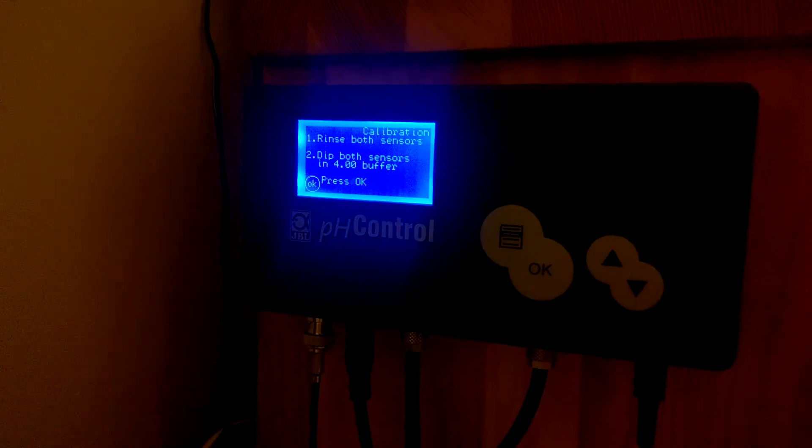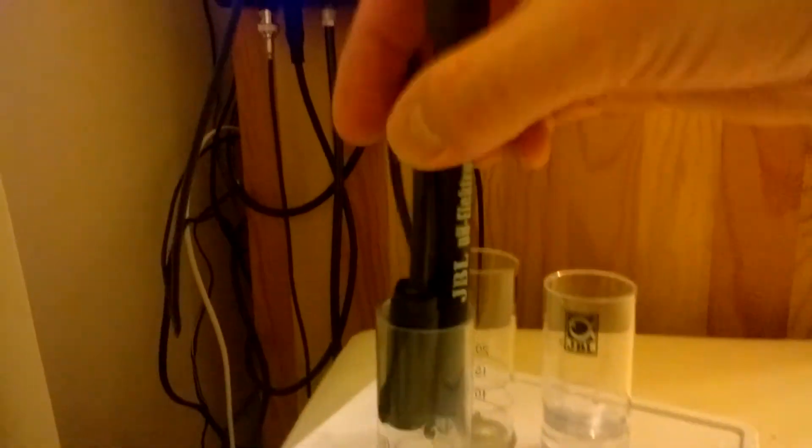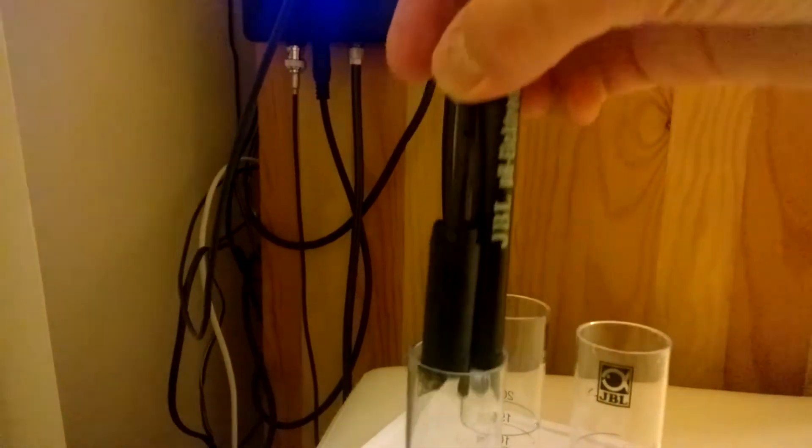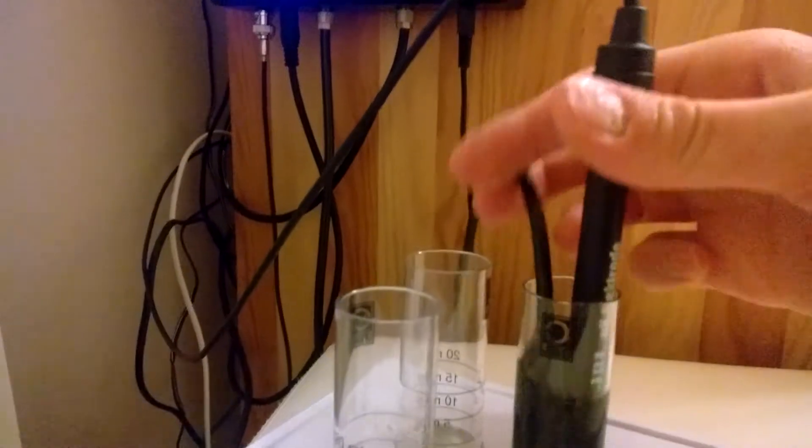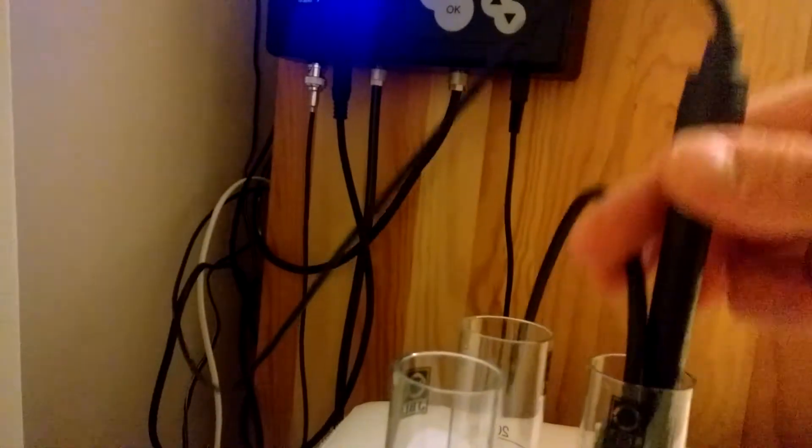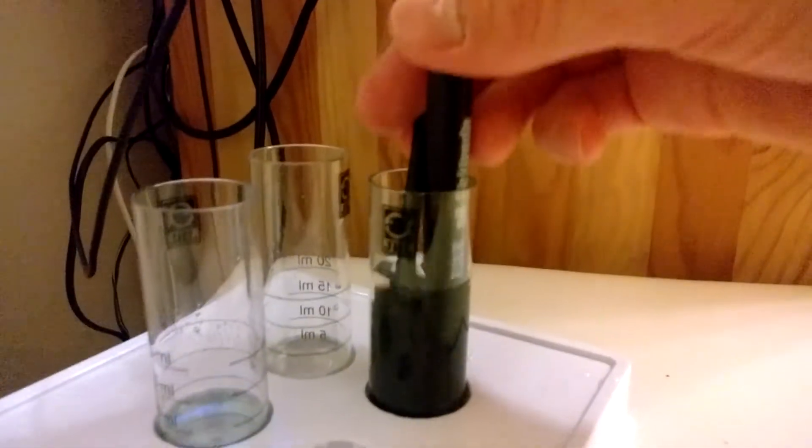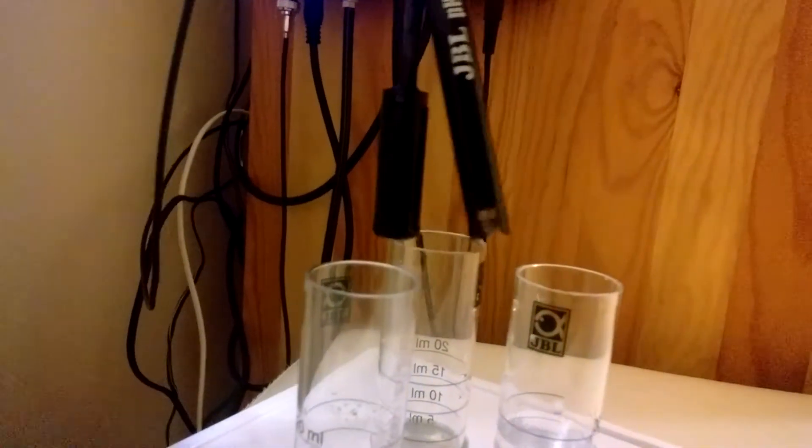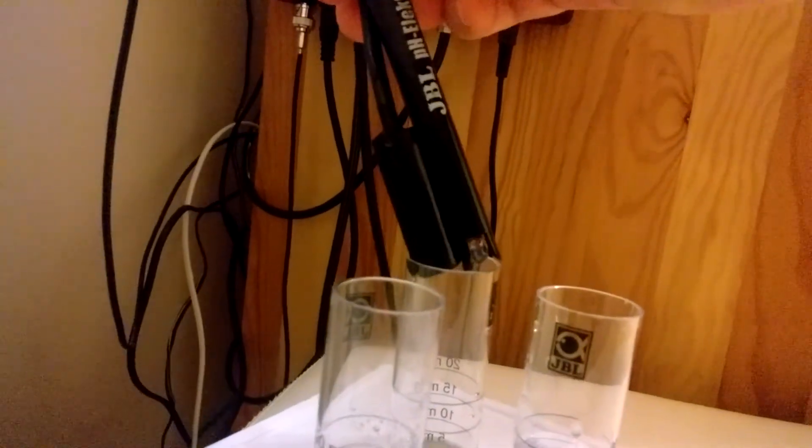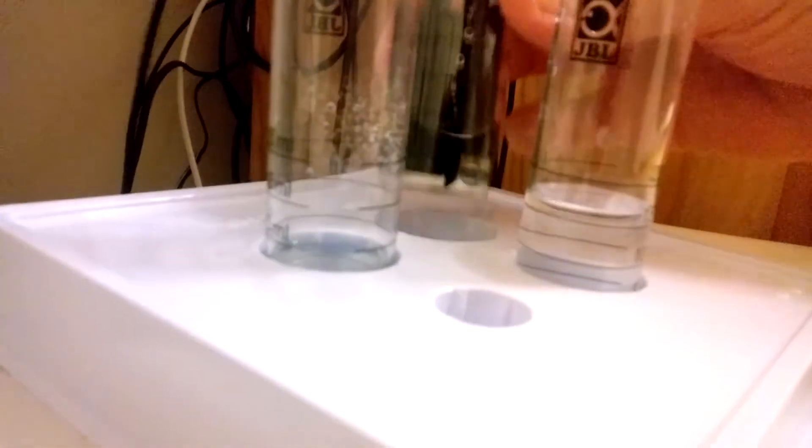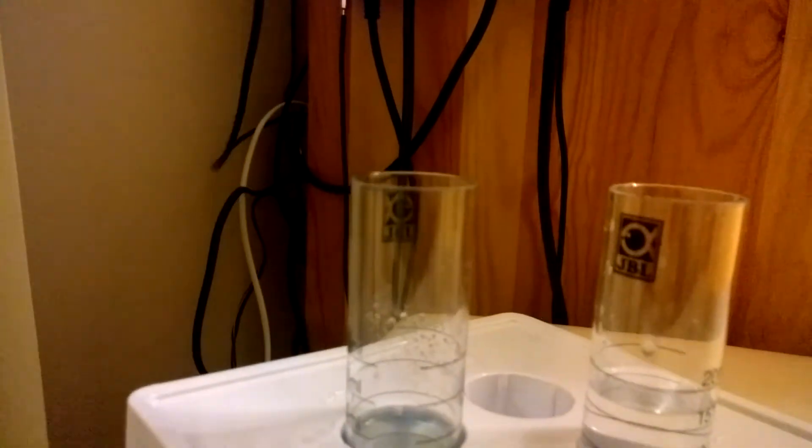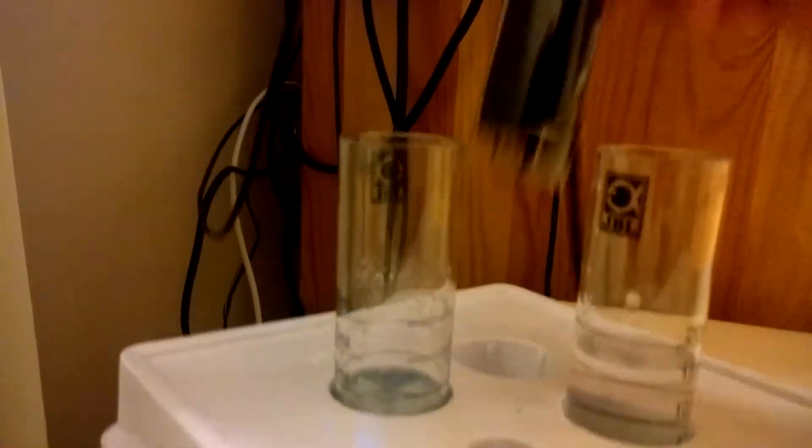And now it says that I need to rinse both sensors in, again, distilled water. And afterwards, I need to put it in the buffer pH 4.0. I'm rinsing. And now I'm putting my sensors in this. Here it is. And press again OK button when it's ready and press OK.